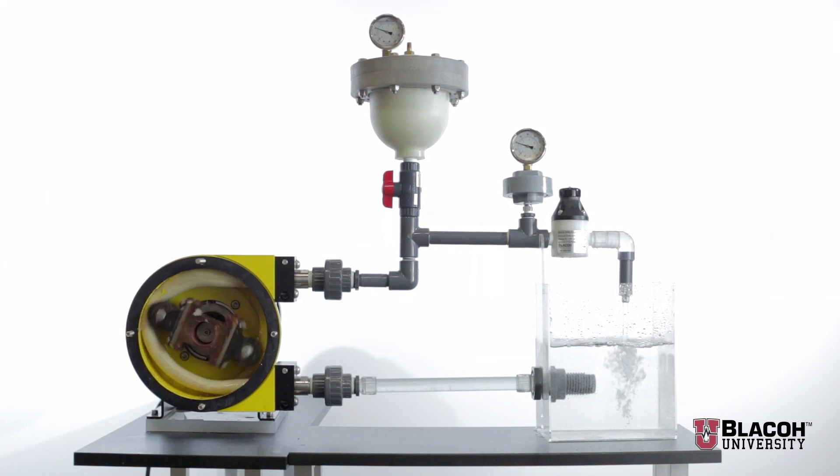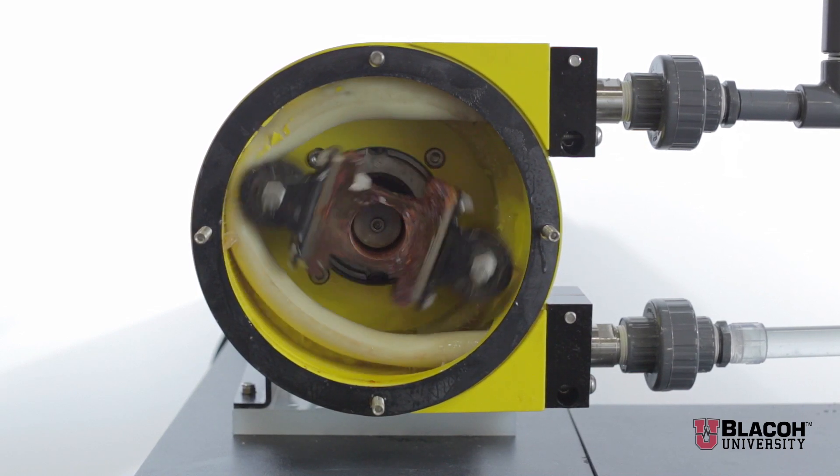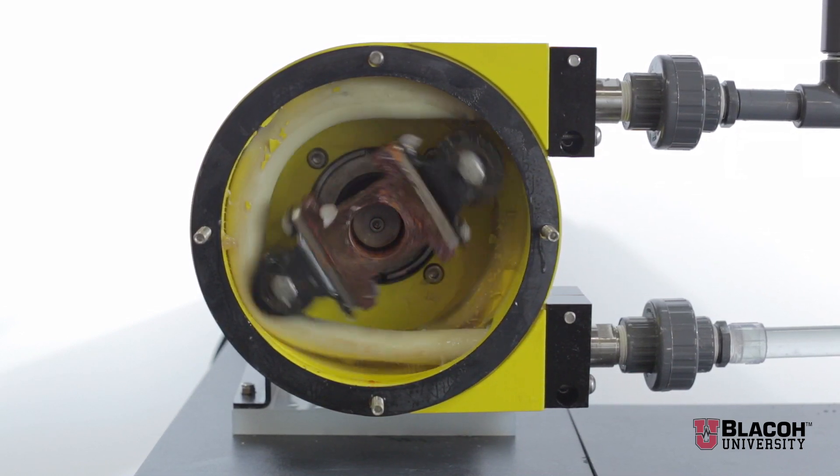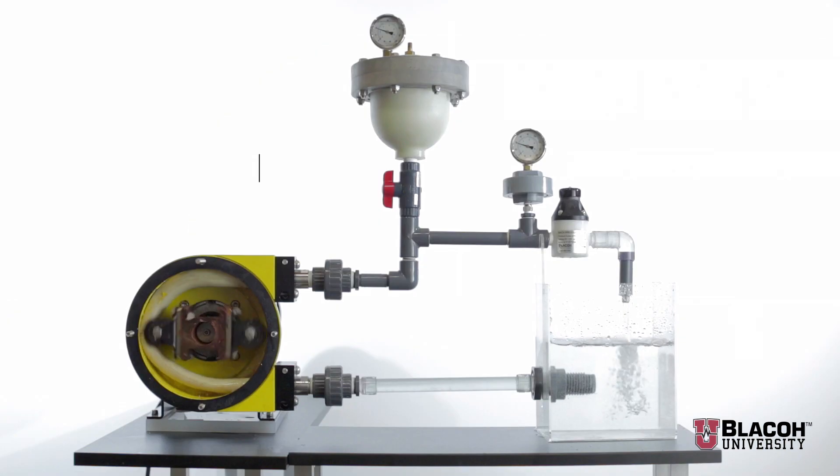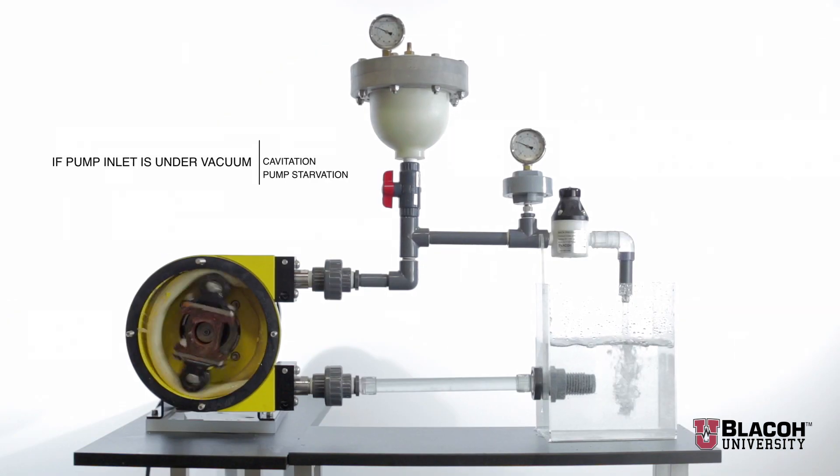If the pump inlet is under positive pressure, acceleration head will cause a pressure spike and vibration, causing potential damage to pipe and components. If the pump inlet is under vacuum, cavitation and pump starvation can occur. These situations can be eliminated or minimized by the installation of Blacoh inlet stabilizers.